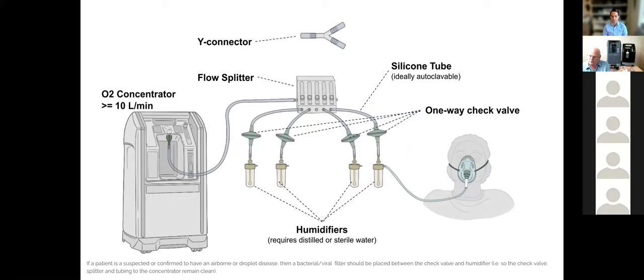And then from the flow splitter, silicon tubing is coming out. It's connecting to the one-way check valves. The one-way check valves, through a short piece of tubing, are going to the humidifiers. And then each humidifier is going to a different patient.